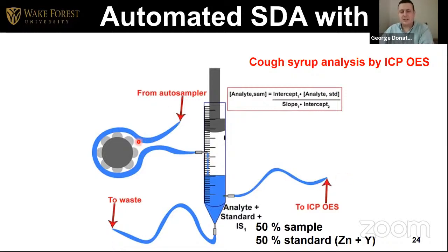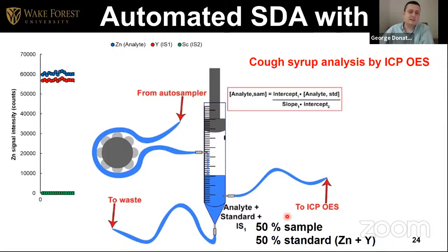Then you change the auto sampler to the second solution. The second solution comes in and starts mixing with the first solution, and then that mix goes to the ICP-OES. So in this example, you have zinc and yttrium. If you look at the graph, the first solution will have half sample, half standard, and the standard will have yttrium, in this example, as the first internal standard, and zinc is the analyte.